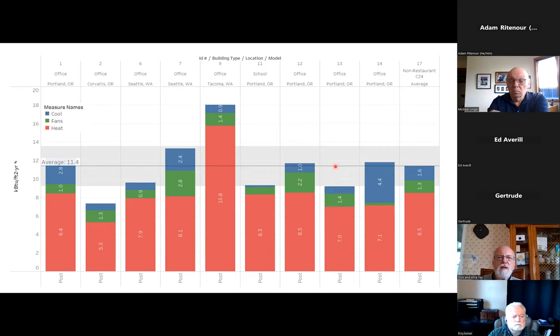So what does that mean? Why is that significant? That means that if you're a building owner in climate zone 4, because again, we got rid of those cold climate projects and those restaurants, and you're a commercial building owner with an energy target, regardless of where you're starting, you know what your HVAC EUI could look like by implementing an HVAC upgrade to VHU DOAS. You can model your energy savings considering that your HVAC EUI is going to be about 11.4 once you're done with the upgrade. Likewise, if you're a utility or an energy efficiency group trying to project the savings from an incentive program or market transformation effort, you can have pretty high confidence in the savings as long as you have a reasonable idea of what the pre-conversion system energy use is.